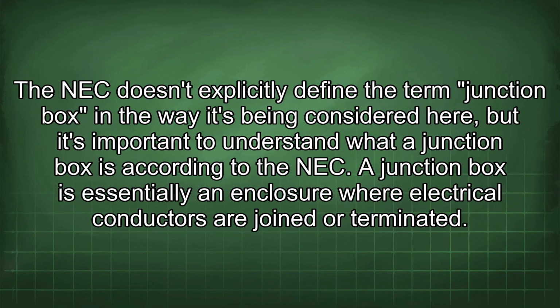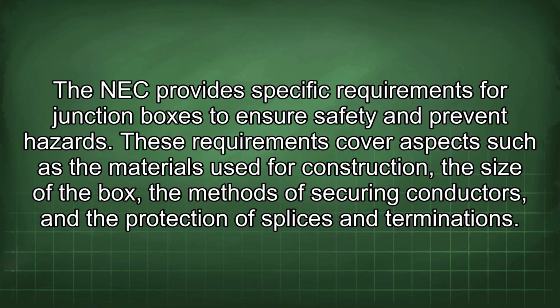The NEC doesn't explicitly define the term junction box in the way it's being considered here, but it's important to understand what a junction box is according to the NEC. A junction box is essentially an enclosure where electrical conductors are joined or terminated. The NEC provides specific requirements for junction boxes to ensure safety and prevent hazards. These requirements cover aspects such as the materials used for construction, the size of the box, the methods of securing conductors, and the protection of splices and terminations.